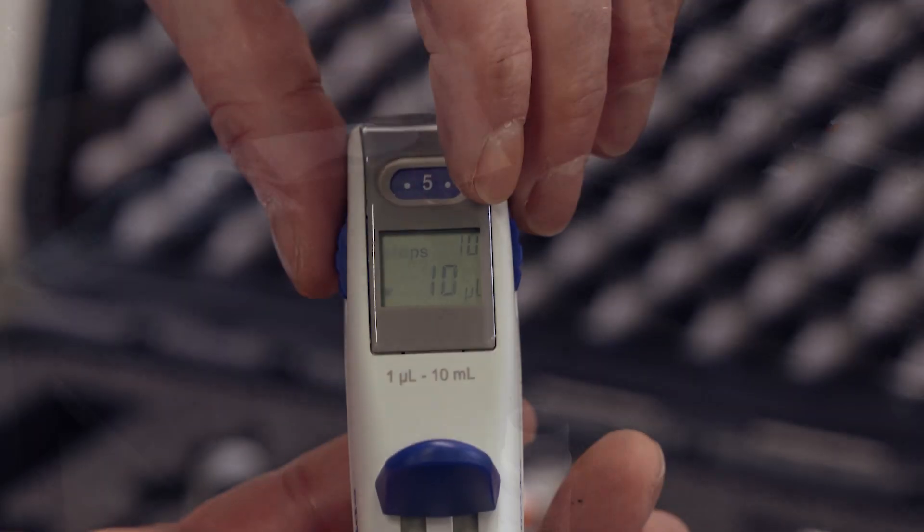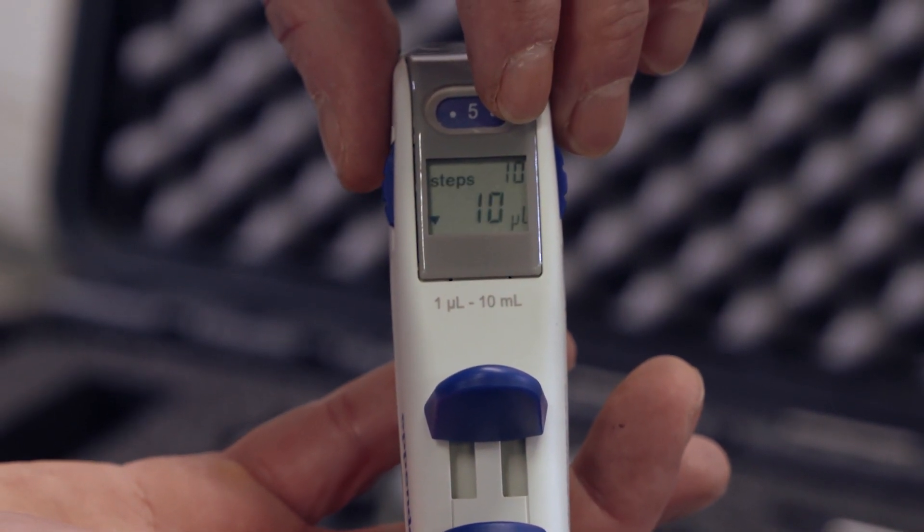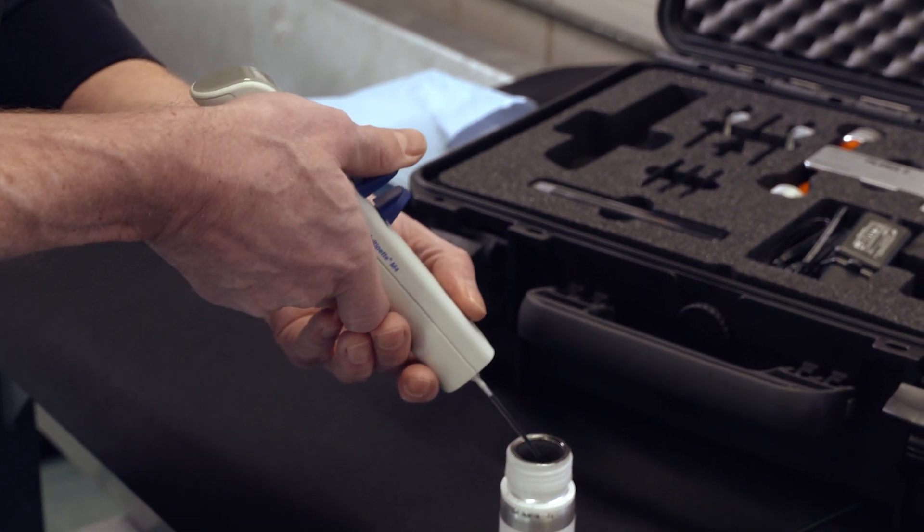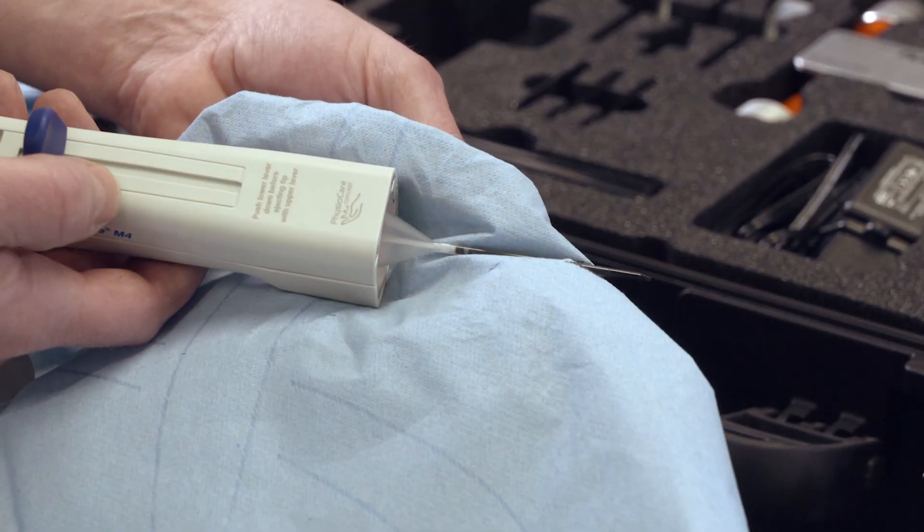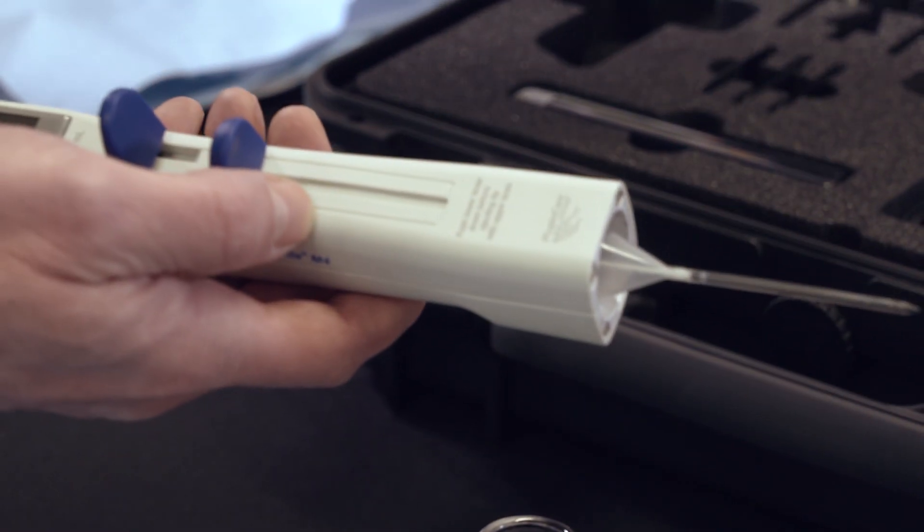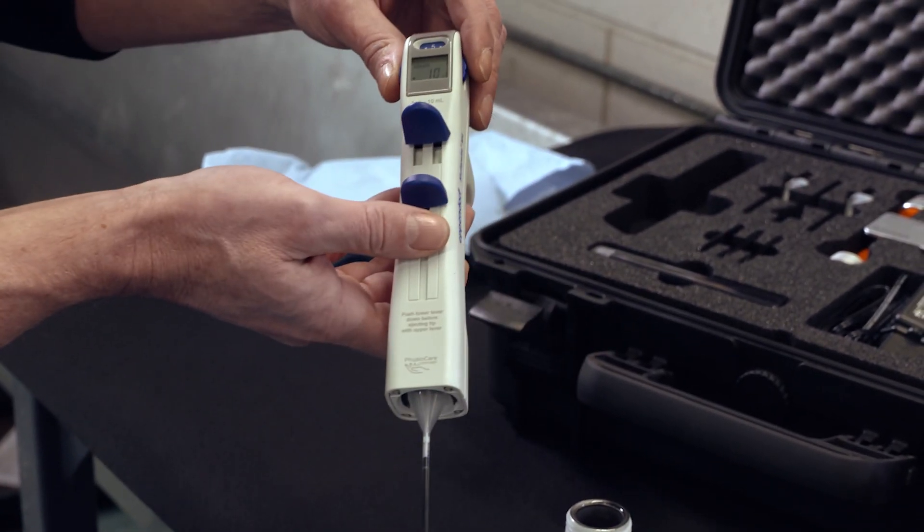After that the display will be flashing. This means that the pipette is not yet calibrated. To fully calibrate it, you must insert the tip into the testing liquid again and this time push the top slide all the way down. Clean the outside of the tip so that there is no extra ink than the exact amount that you set the dial to. Now the pipette is fully calibrated.